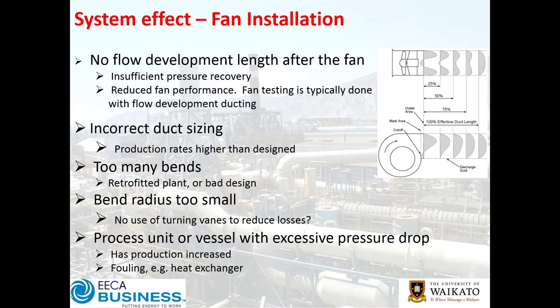Carrying on downstream from the fan: if we don't allow for flow development after the fan, we're not going to get sufficient pressure recovery, ultimately leading to reduced fan performance. When you look at the fine print of a fan curve — often cut off when photocopied into your manual — it stipulates that the fan curve is for that fan with a particular installation configuration.